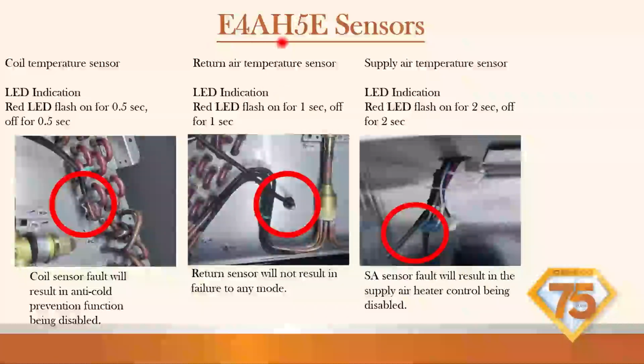This is the E4AH5E air handler. So we've got a coil temperature sensor. We've got LED indication. It's got a red LED that flashes on for 0.5 seconds and off for 0.5 seconds. A coil sensor fault will result in the anti-cold prevention function being disabled. We'll go over that anti-cold function, but that is sensing the coil temperature.